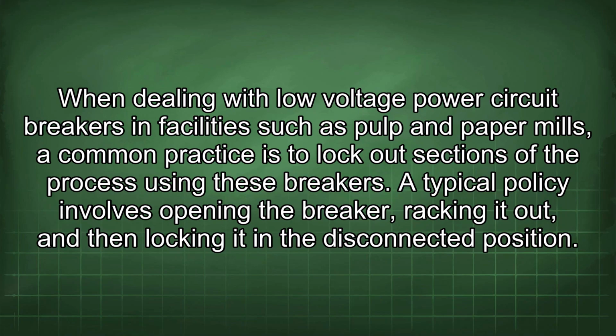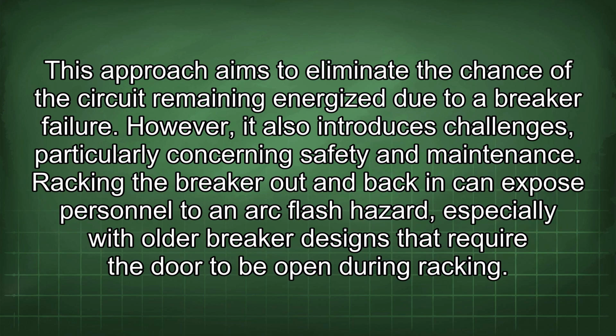When dealing with low-voltage power circuit breakers in facilities such as pulp and paper mills, a common practice is to lock out sections of the process using these breakers. A typical policy involves opening the breaker, racking it out, and then locking it in the disconnected position. This approach aims to eliminate the chance of the circuit remaining energized due to a breaker failure. However, it also introduces challenges, particularly concerning safety and maintenance.